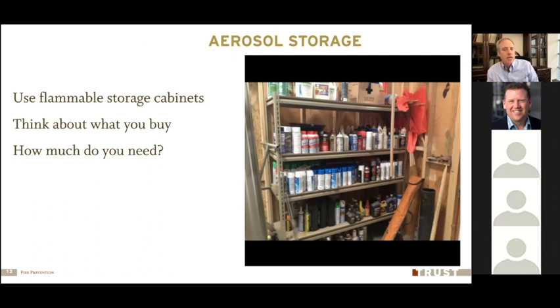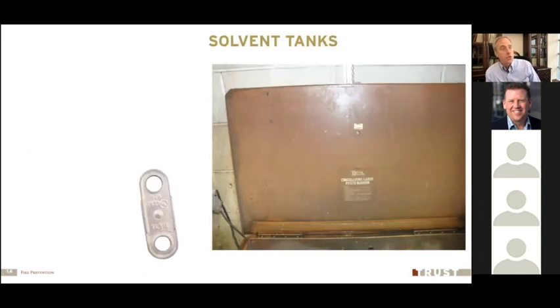Check the chemicals as you're getting them and see if they're flammable, so you know ahead of time how you need to store them. And think about alternatives to flammable materials, if there's another chemical that you can get that'll do the same job that doesn't present that potential fire hazard. And another thing is, think about how much you need. Often we'll see just years and years and years of supply of these different flammable aerosols, whether it's paint remover or spray paints themselves, and we do use a lot of that material, but maybe we store it more than we actually need for a reasonable amount of time. And so if you can cut back on your inventory, that's another way to help prevent a fire, or to prevent a fire from getting worse than it needs to be.